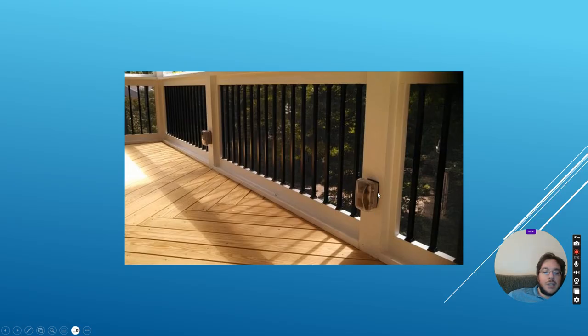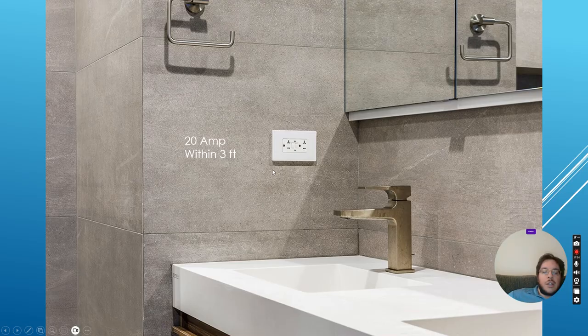And if you've got a balcony, then you need receptacles on the balcony, and they must tie in to the outdoor circuit, or they can be on their own circuit, doesn't matter. But you can't put outdoor receptacles and indoor receptacles on the same circuit. That's the bottom line. Now, in the washroom, you must have one 20 amp receptacle next to the sink.